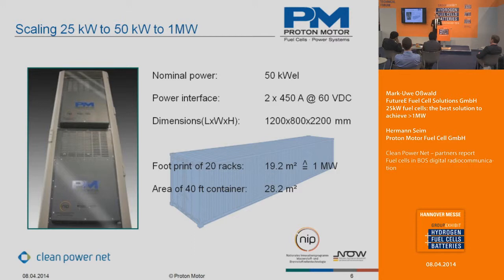Sounds very simple, and in fact it is, because the footprint of these 20 racks is just 19.2 square meters. If we look at another real industry standard, like a 40-foot container, with an internal ground area or floor area of 28.2 square meters, we already checked this — we will get this 1 megawatt into one of these containers.